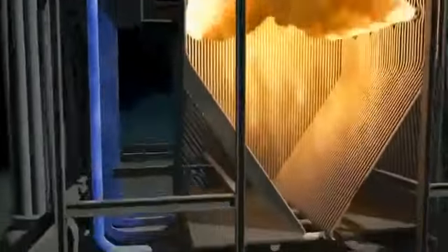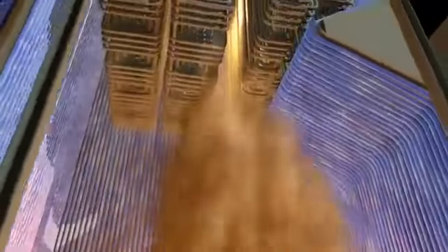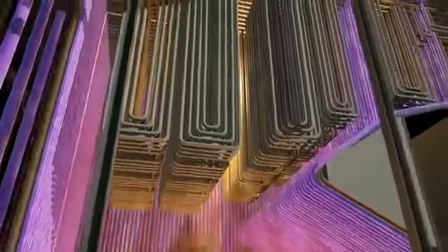Liquid water flows through large downcomers and into the base of the firebox. A network of 2-inch tubes line the firebox walls, and burners force-feed a continuous supply of combustible fuel into the ultra-hot firebox. Eventually, the insides of the firebox burn so hot that its surrounding steel walls would melt if not for the tube-lined walls of liquid water.